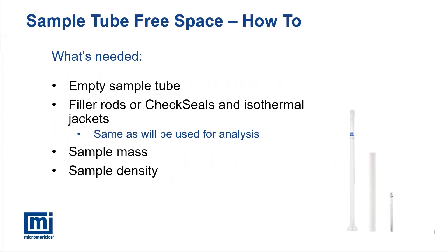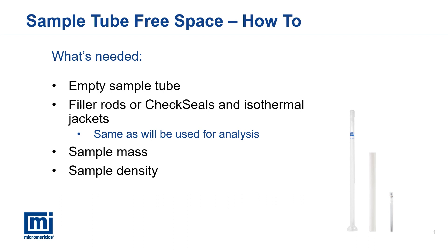The new sample tube free space feature on the MicroMeritics gas adsorption instruments enables users to determine the volume of an empty sample tube using alternative gases to the traditional helium. The calibrated empty sample tubes can then be applied to sample analysis files to calculate free space by subtracting the quantity of gas displaced by the sample from the empty sample tube free space. We will need empty sample tubes fitted with the same accessories to be used for sample analysis, the sample mass, and the material's skeletal density.